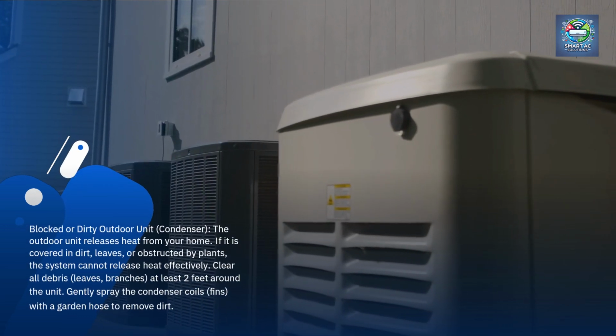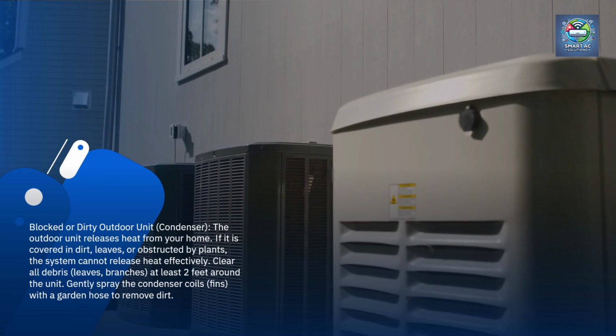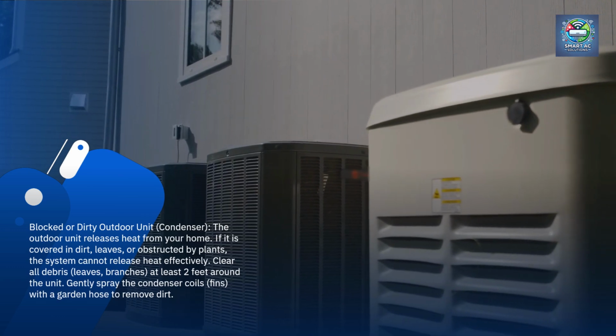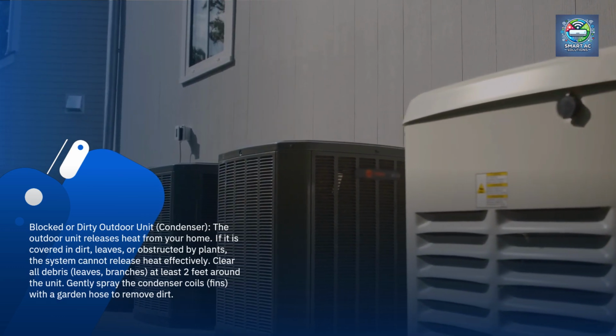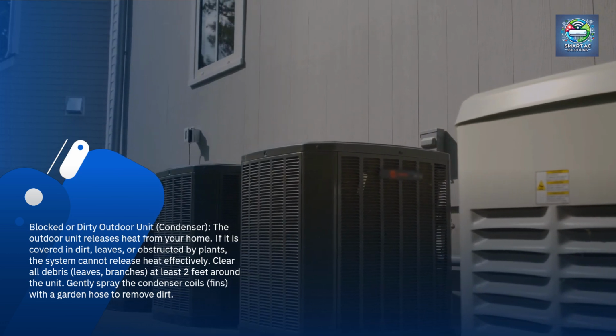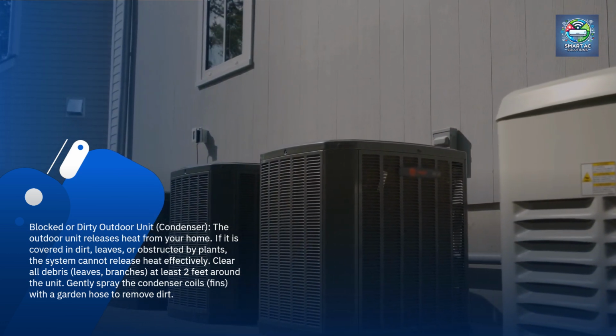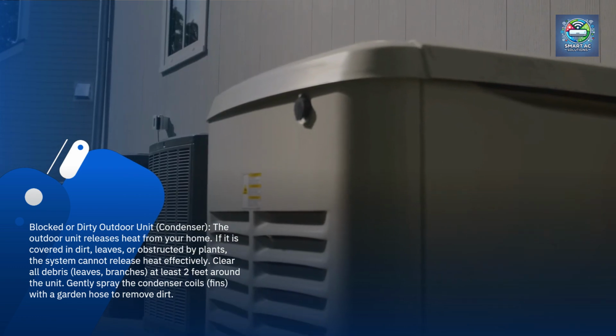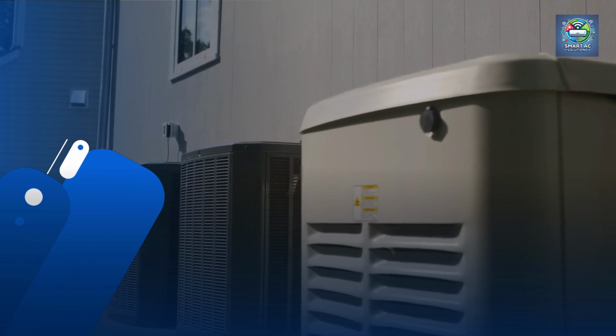Blocked or dirty outdoor unit, condenser. The outdoor unit releases heat from your home. If it is covered in dirt, leaves, or obstructed by plants, the system cannot release heat effectively. Clear all debris, leaves, and branches at least 2 feet around the unit. Gently spray the condenser coils, fins, with a garden hose to remove dirt.